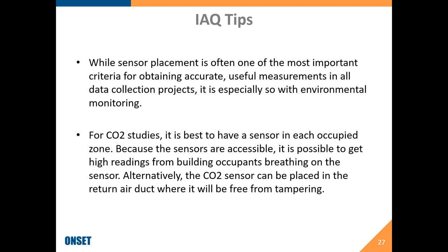So it's really important that you take into consideration all of those factors when deploying these air quality monitors for accurate testing. For CO2 studies, it's always best to have a sensor in each occupied zone. But as the sensors are accessible, there is a risk of people tampering with them. We've dealt with cases where people breathe on the sensor, which will significantly skew the reading. So sometimes we'll recommend putting them in an air duct or an out of reach place in that occupied zone.